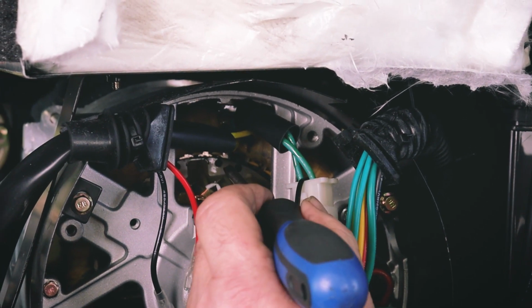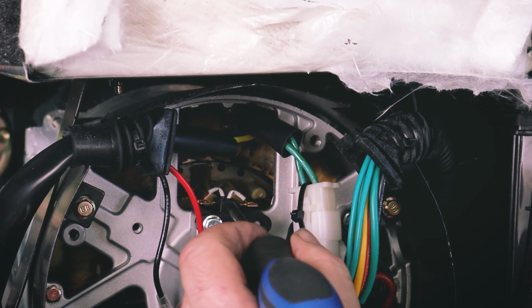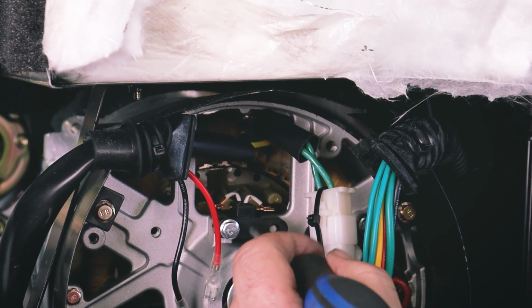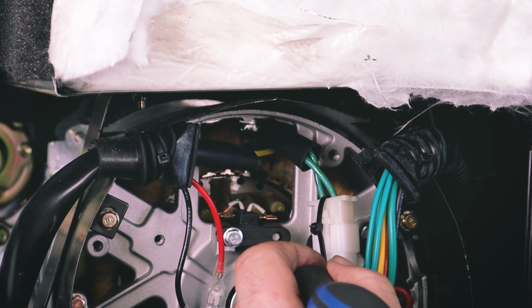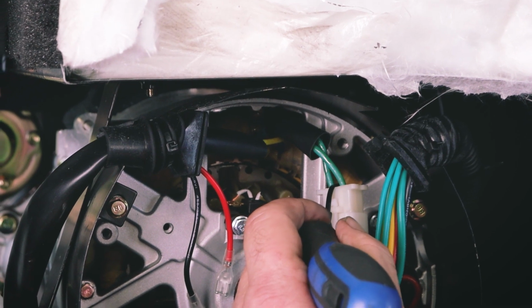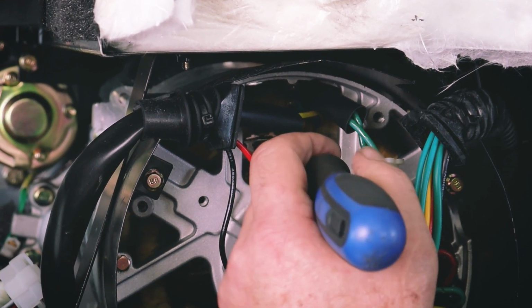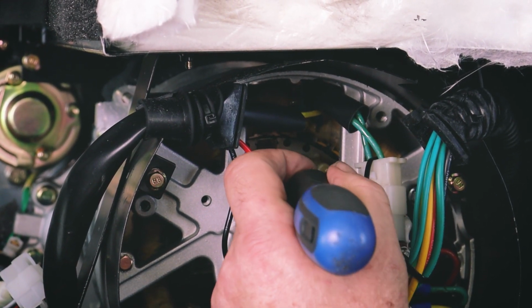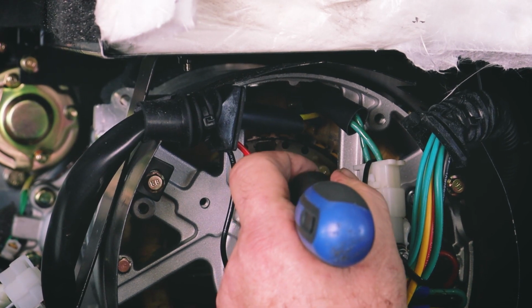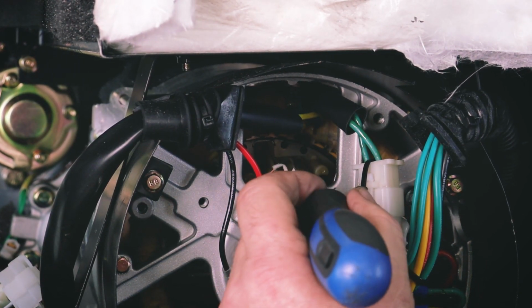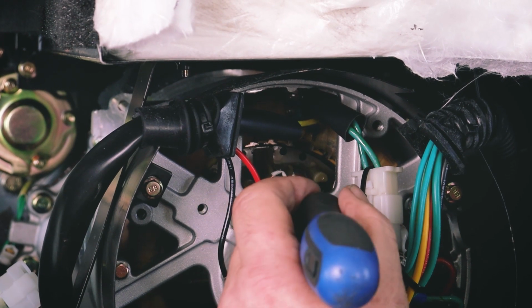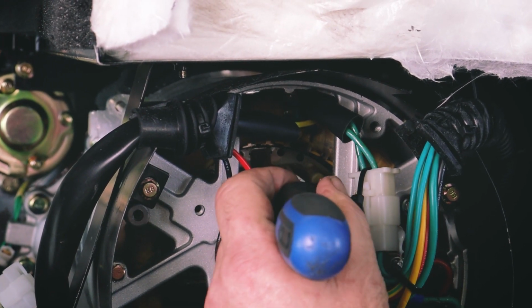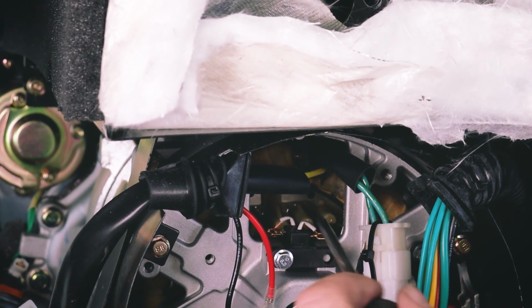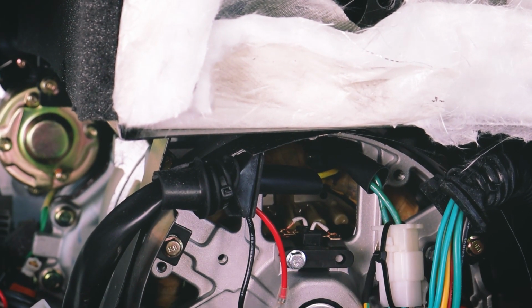If you see this wire is very low, that means the brush has worn away and pulled the wire down with it towards the slip rings, and that's a good indicator that the brushes may be worn out. You could give these a little pull just to check there's no broken wire in here. If you give that a little lift on both sides and it just slides out, then pretty much there's a broken wire, and the issue could just be the brushes.